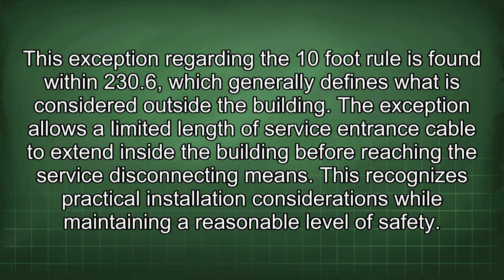This exception regarding the 10-foot rule is found within 230.6, which generally defines what is considered outside the building. The exception allows a limited length of service entrance cable to extend inside the building before reaching the service disconnecting means. This recognizes practical installation considerations while maintaining a reasonable level of safety.